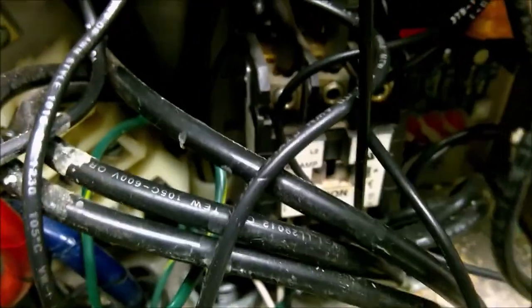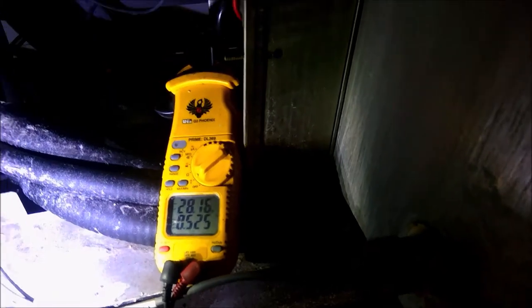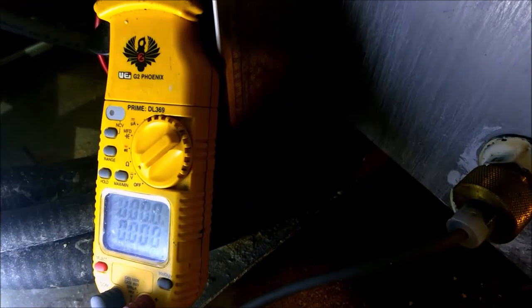We do have proper coil voltage at this point. Now I'm going to move over to the element. This is on the left hand side of the unit. I have 28 amps. I'm going to test all the legs here and make sure they're all drawing. It's really tight here. 28 amps, so we're good here on all the legs.